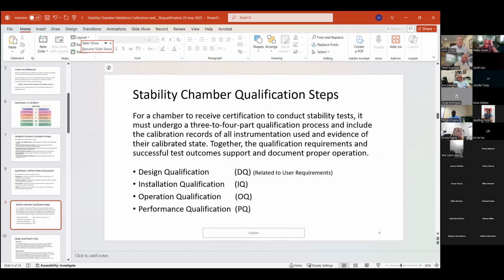Qualification steps for a chamber to receive certification to conduct stability tests must undergo a 3 to 4 part qualification process and include the calibration records of all the instruments used and evidence of their calibrated state. And together, the qualification requirements and successful test outcomes support and document the proper operation. I said 3 to 4, and that's because that first one, design qualification, often gets left out in these kinds of discussions. People talk about the IQ, OQ, and PQ, and we'll do that today, but I didn't want to skip over design qualification. And we'll take a look at that in detail here.